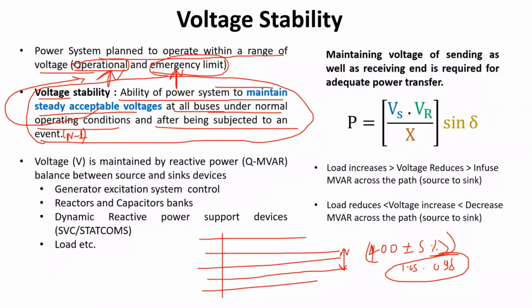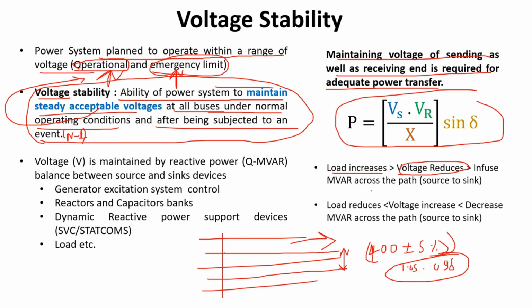For maintaining the voltage of sending as well as receiving end for the required active power, we have already discussed this in the equation. Now we will see what happens when there are changes in the system load, when the load increases and when it reduces. We already know that if you increase the load in the system, your voltage is going to reduce because the transmission line loading is going to increase. If the line loading goes above surge impedance loading, it is trying to absorb more reactive power, and therefore you have to infuse MVAR into the path. You have to increase the voltage for the same amount of power transfer. You can easily see this from the equation itself. When the load reduces, voltage increases, and MVAR across the path decreases, so you have to absorb the reactive power from the system. You have to put a reactor into the system.